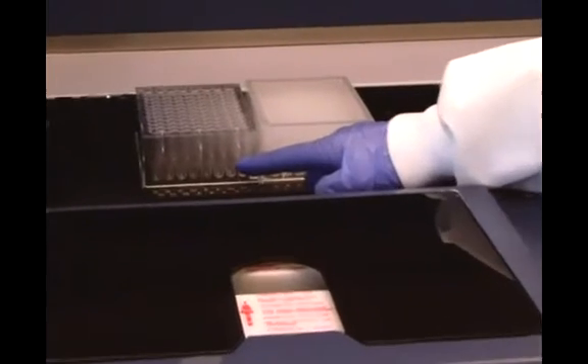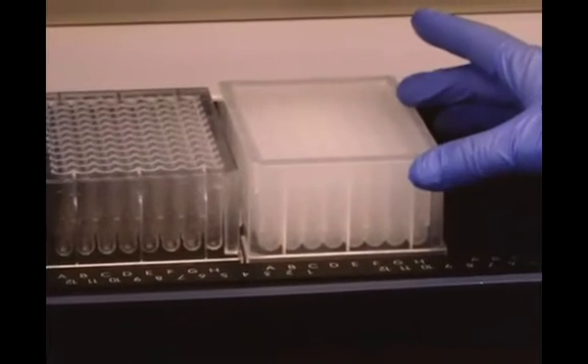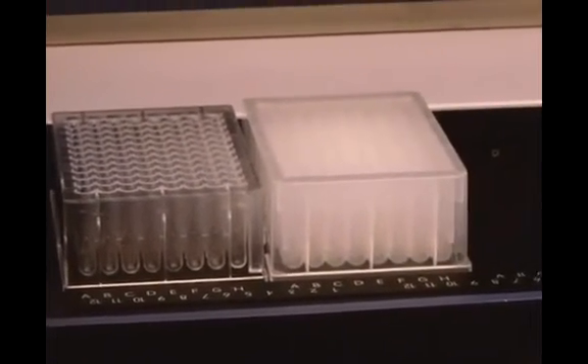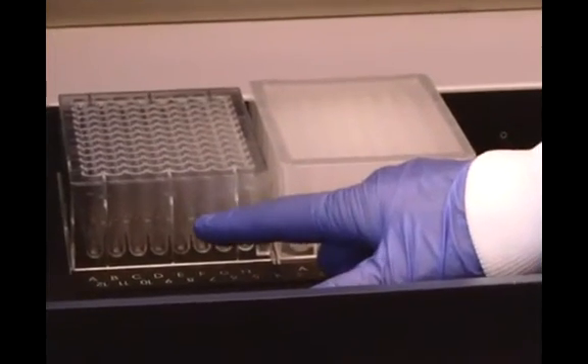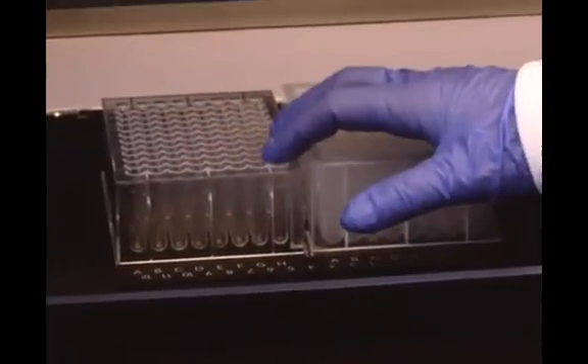One of them is called an intermediate plate, and the other one is called an archive plate. The archive plate will be frozen and saved for about 30 days or so. The intermediate plate is really the working plate.